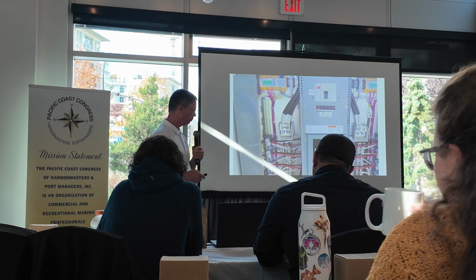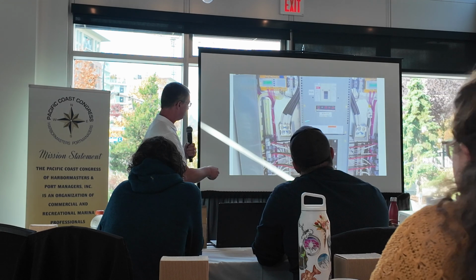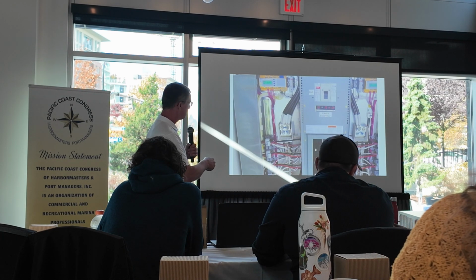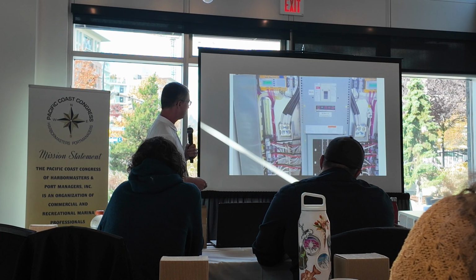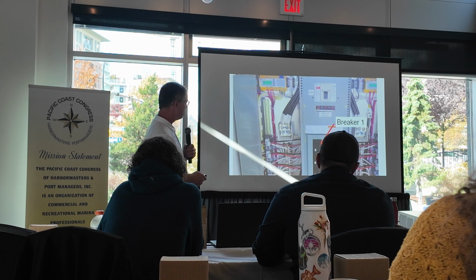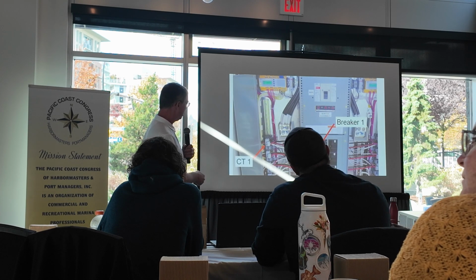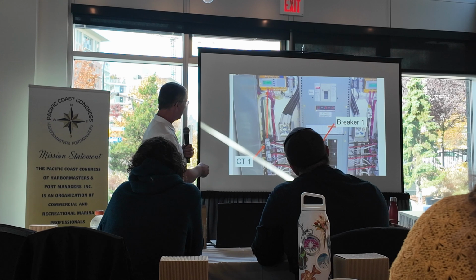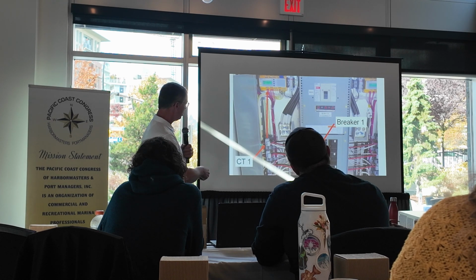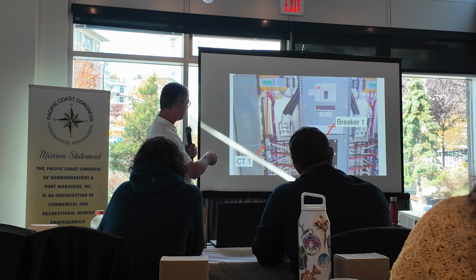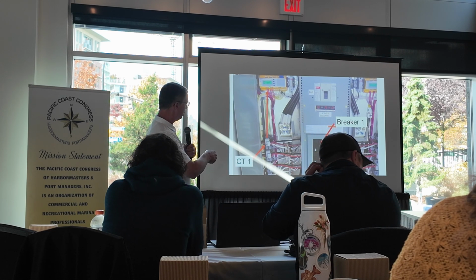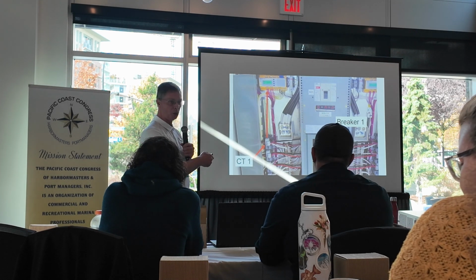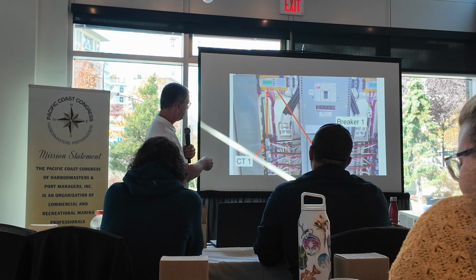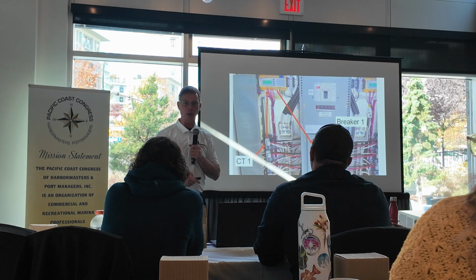Well, this was very interesting. The wiring job is actually not bad. You've got 2 Bender units up here, with 12 channels. You've got breaker 1, CT 1, and channel 1 up here. That CT looks for leakage current. It will tell this unit, hey, channel 1 has leakage above the set point, which is generally 100 milliamps in this case, and it should trip the shunt trip mechanism on that breaker and de-energize that circuit.